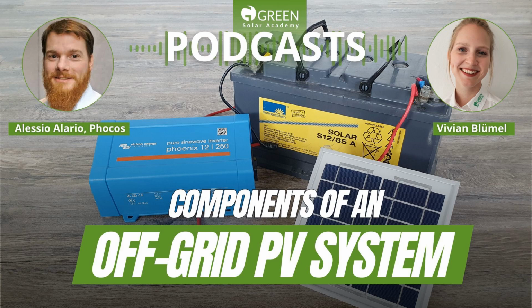So, there's various stages in charging. There's usually a boost stage, a float stage, sometimes an equalization stage. So the charge controller needs to be capable of handling all those different voltages and currents that your battery requires to be properly charged. And by properly charged, I mean not only getting your battery full, but making sure that when it's not being used so much that it can be in a float stage almost indefinitely. So we need to make sure that the battery is fully charged, but also make sure that we increase the life expectancy by making sure that we're being conservative in the voltages that we're giving to the battery if it's for long term.